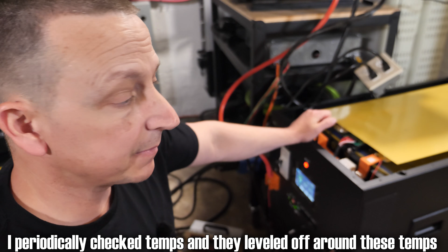The bus bar coming off of cell 16 is 140. Down at the fuse it's still doing 235, 236. The bus bar right after it is 192 degrees Fahrenheit. So the bus bar went up a couple degrees, maybe 5, but the fuse temperature is staying about the same. I can still grab onto the battery cables up here, so those aren't too hot.